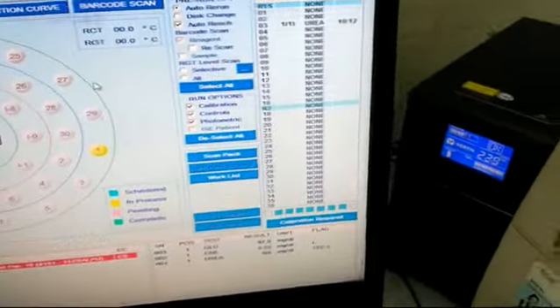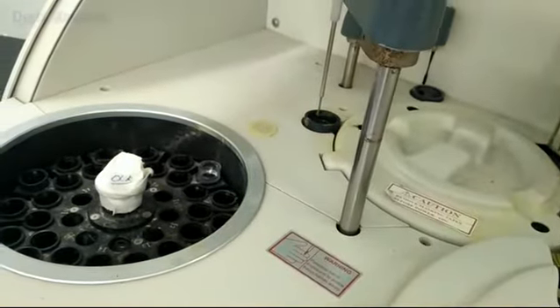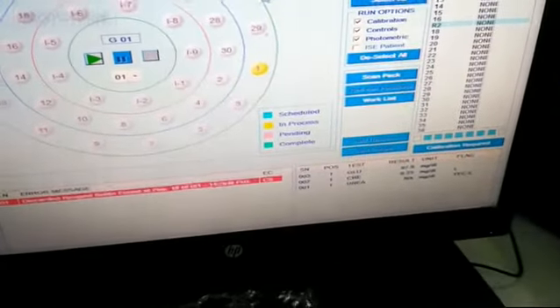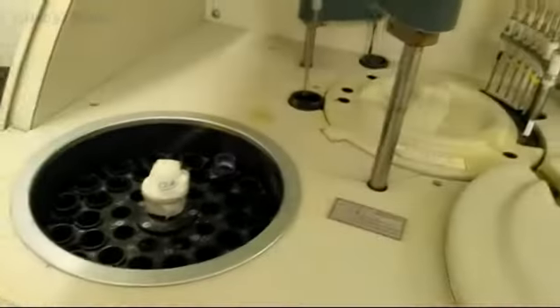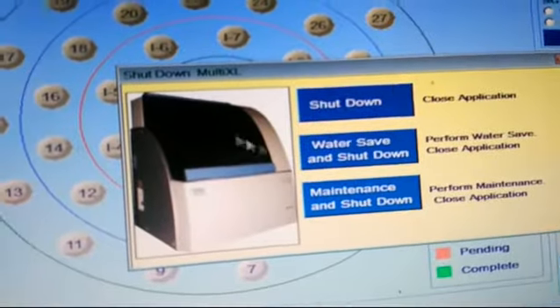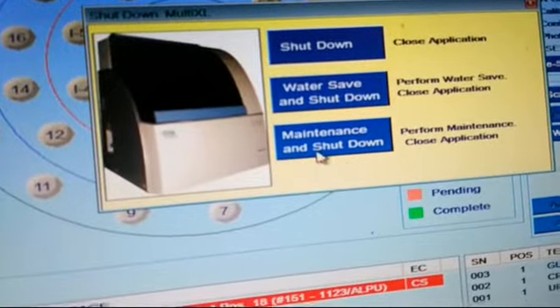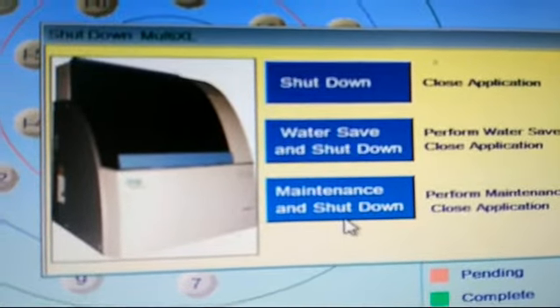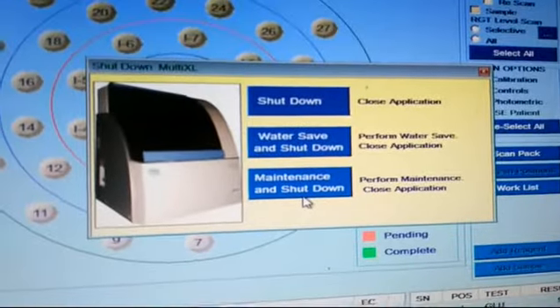Then we are going to demonstrate the shutdown procedure. At the end of the day, you have to properly shut down this machine. So there is the option for shutdown. Okay, this is the shutdown option, and by clicking shutdown, there are three types of shutdown: shutdown, water save and shutdown, and maintenance and shutdown. We don't recommend the plain shutdown anymore. We recommend the water save and shutdown and the maintenance and shutdown.